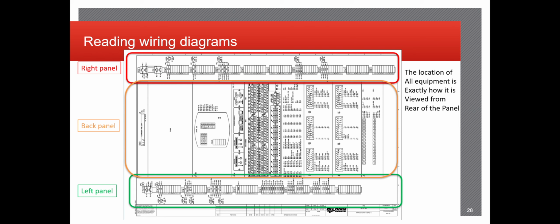So you're always going to be looking at the back side of the panel when you're looking at a wiring diagram. The back of the panel is where you access all the nodes to all the relays, all the backs of the test switches, and where you'll access the terminal blocks. At the front of the panel, you can see the front face of the relay, the actual knives of the knife switches, and then the mechanical operative pieces of the lockout relays and whatever else may be in there. But the terminal blocks you can usually only get to in the back of the panels, and that's because there's no real operation to begin with. It's just a junction point for wiring to enter and exit.